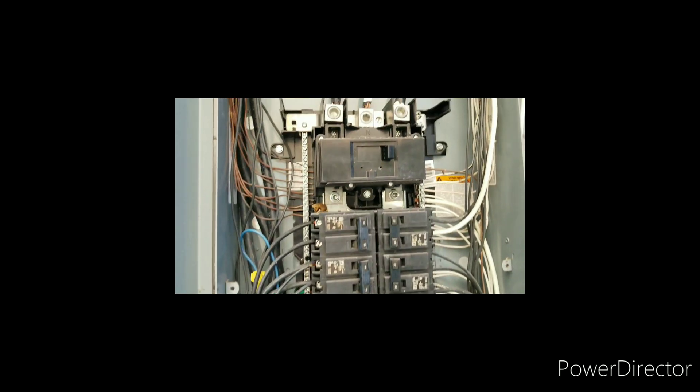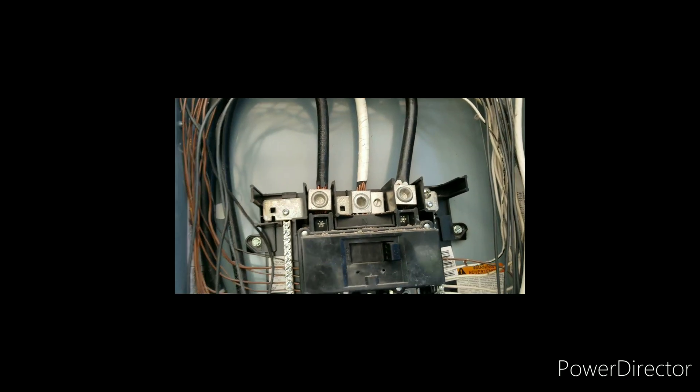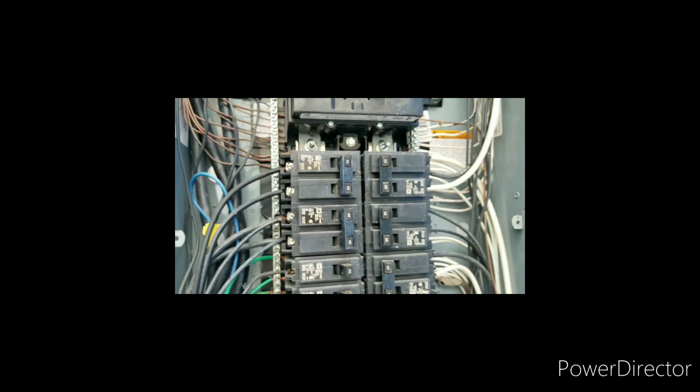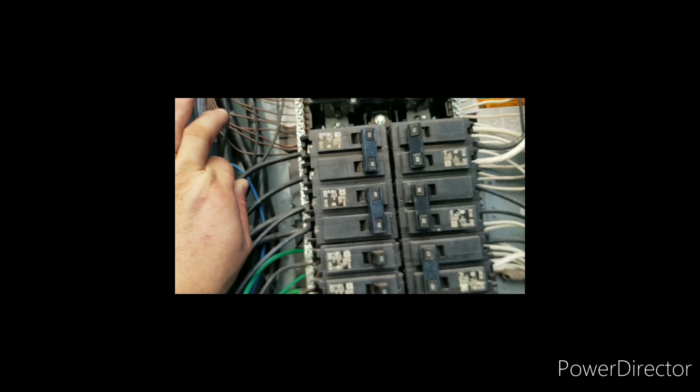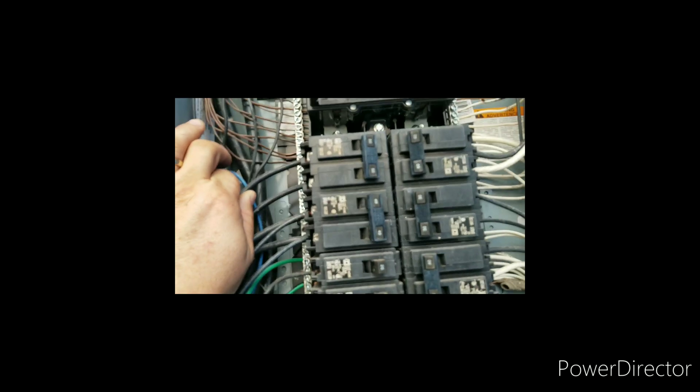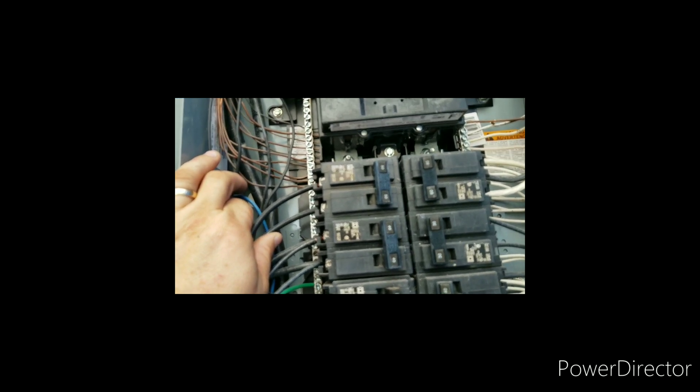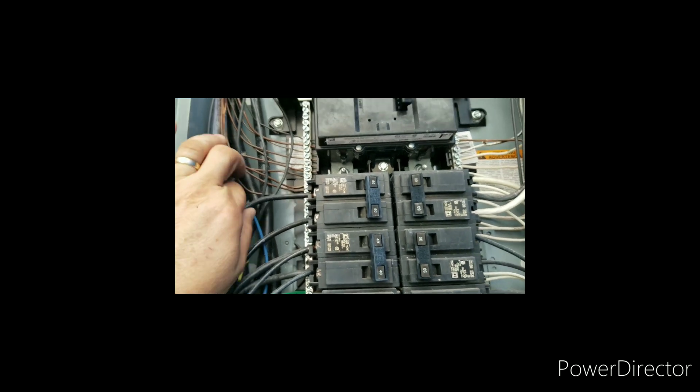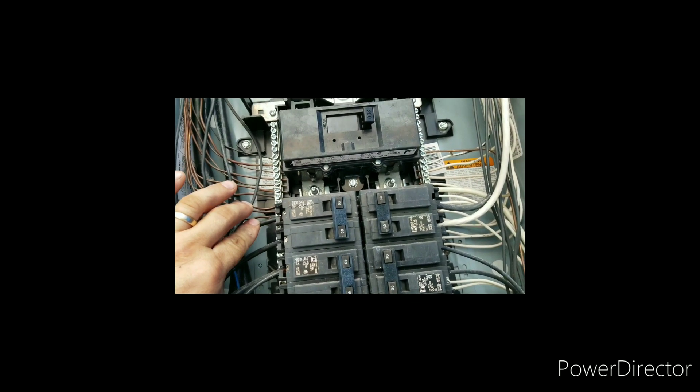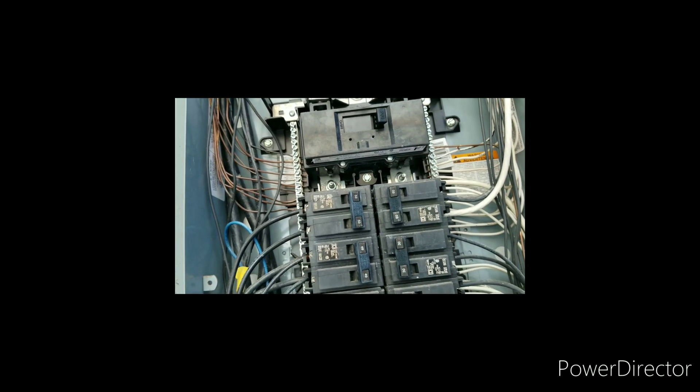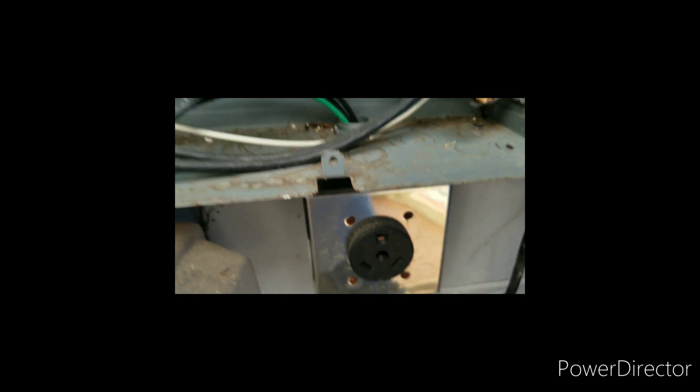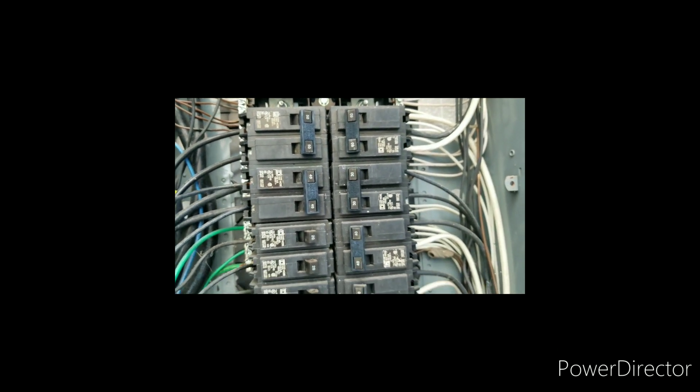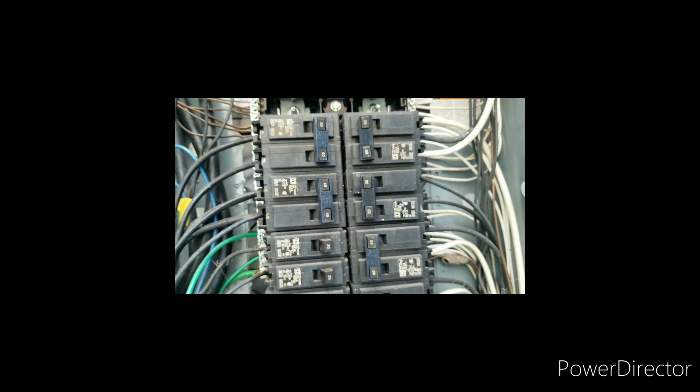I've got a 200 amp main, so the big CTs that it came with will go on there. Then what it's able to do is I put one of the CTs on a 220, as long as it has a similar ampacity or current draw. The software in it will allow you to double it, so you only need to put one on your 220s. So in this case, this guy here is double tapped, probably shouldn't be, but it's just running a back feed for a generator or I could run this kiln off of it. But that's my air handler, I believe. Sorry, my range. That's my range. So it's not like I'm going to be using my range while I'm trying to use my kiln or whether or not I need to.